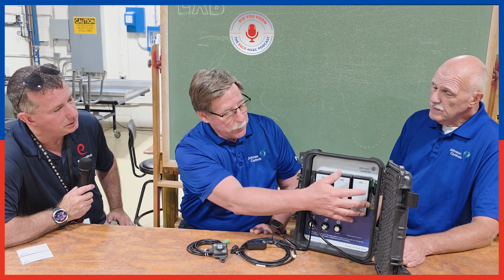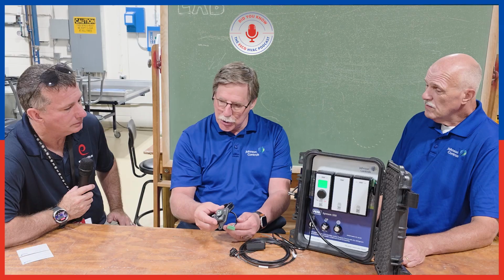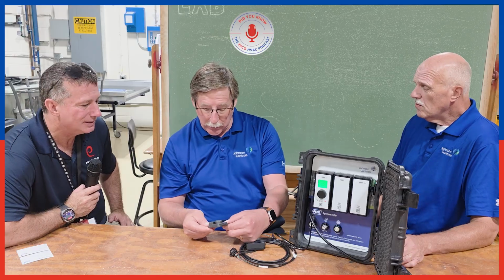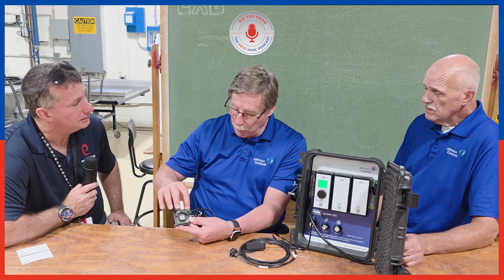That's right. Not only that, but the backplane is communicating from the controller to the expansion modules via Modbus, and that's what gives us the intelligent A2L leak detection and mitigation, because it's doing a handshake with 1 or more A2L sensors. Really? So it knows, you can see on this particular sensor here, that the refrigerant type R454A is marked on the sensor. The OEM that integrates this into their equipment will also select the refrigerant that they're using, and it's going to do a handshake with the sensor to make sure that you've plugged in the right sensor. So it's a communicating network. And it's a communicating network, correct.